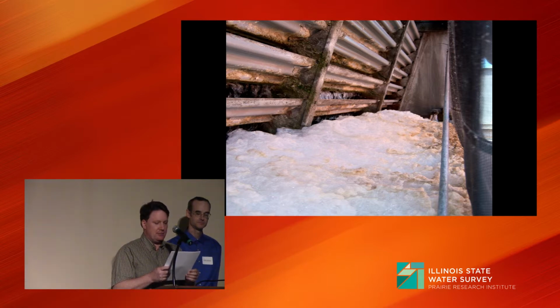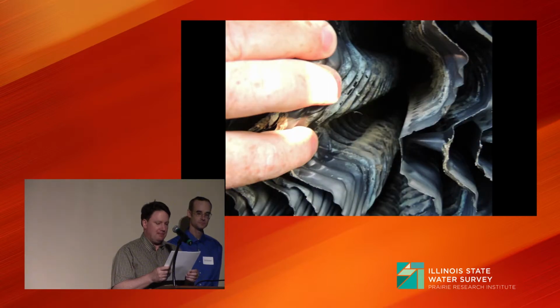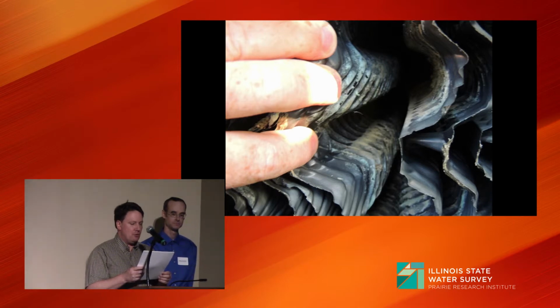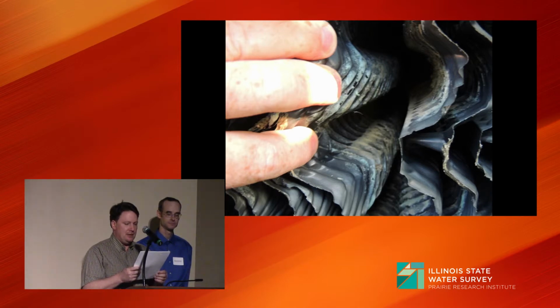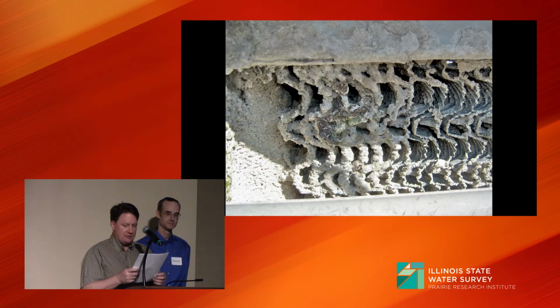Scale formation is another problem, especially in cooling towers, which can evaporate thousands of gallons per day. Keep in mind, here in Champaign, every 1,000 gallons of water carries 3/4 of a pound of minerals with it. So here's a picture of internal tower fill. It's not too dirty. And this is what it looks like when it all goes terribly wrong. A poorly run cooling tower is the equivalent of a limestone factory. This greatly reduces the efficiency of the cooling system and results in much higher energy usage, plus cleaning and repair costs.